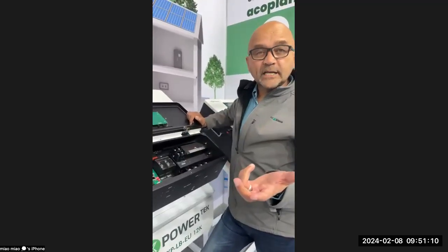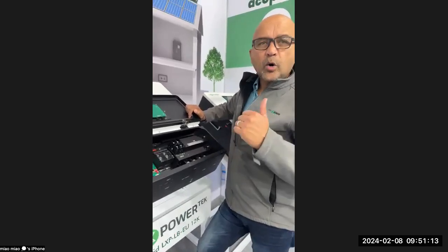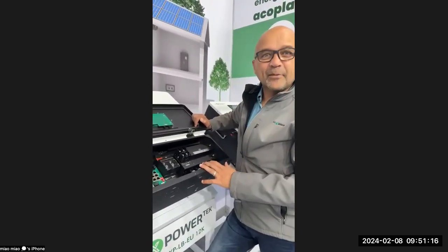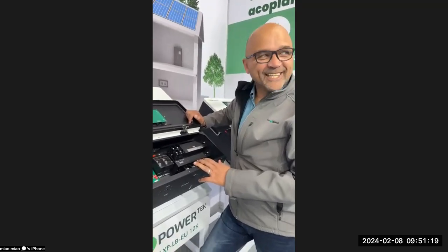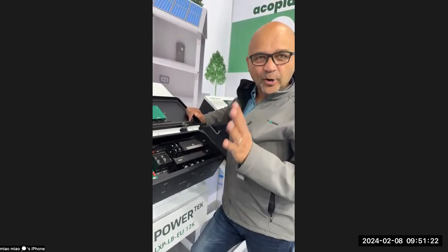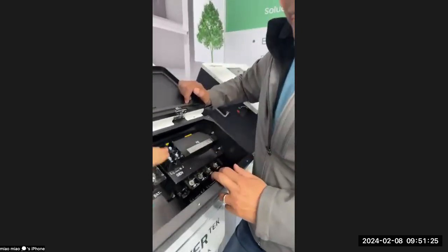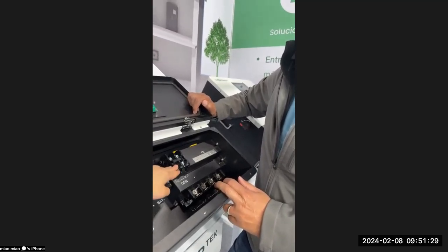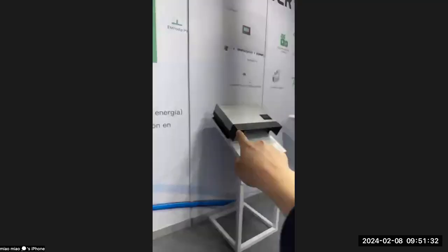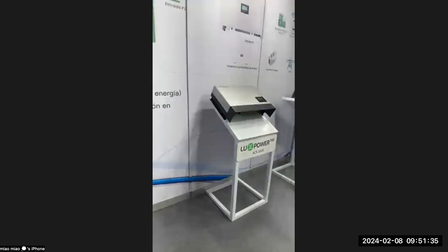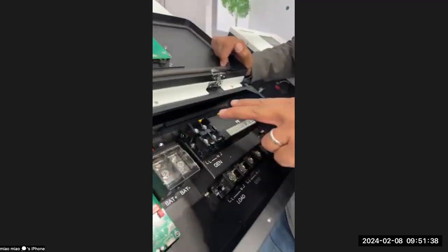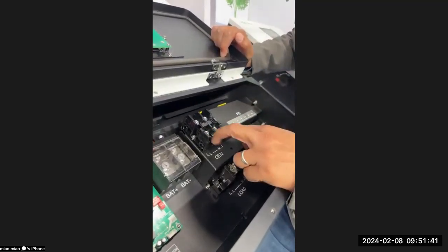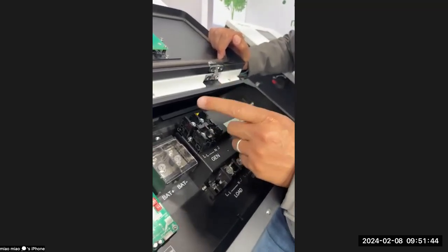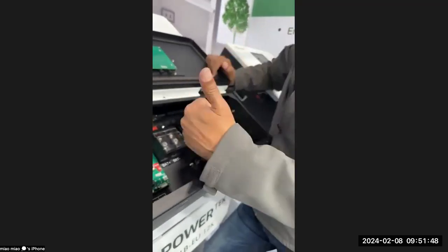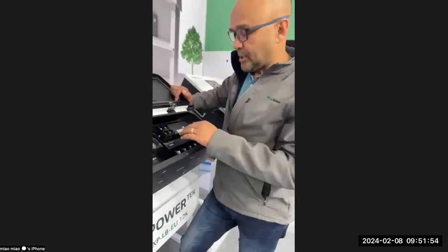The same thing with if you're using a grid-tied inverter like a Sunny Boy, whatever other brand. I'm not going to give them airtime on our show, but a grid-tied inverter that is purely PV. The Gen port, when it works with the AC coupling function, works exactly the same. So here you can fit your microinverter, you can fit your grid-tied inverter here, but you have to enable the feature on the app, which is the smart load feature. So you can either enable it as an AC couple, or as a generator input, or as a smart load port. And I'm going to get to the smart load port in a minute.